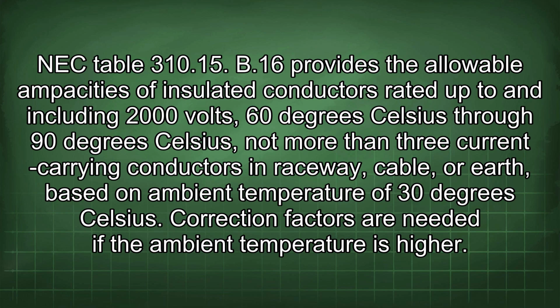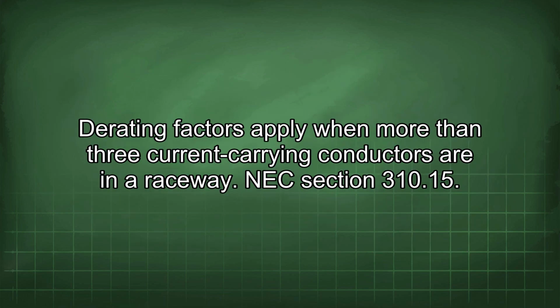B16 provides the allowable ampacities of insulated conductors rated up to and including 2000 volts, 60 degrees Celsius through 90 degrees Celsius, not more than 3 current carrying conductors in raceway, cable, or earth, based on ambient temperature of 30 degrees Celsius. Correction factors are needed if the ambient temperature is higher. Derating factors apply when more than 3 current carrying conductors are in a raceway.